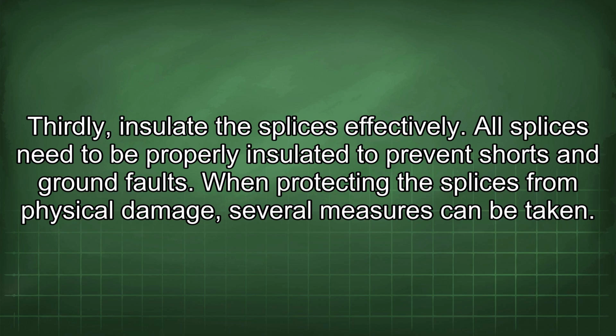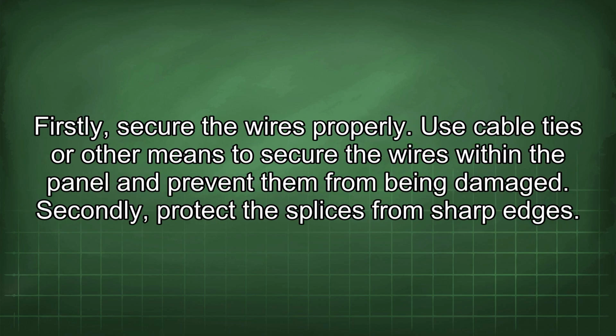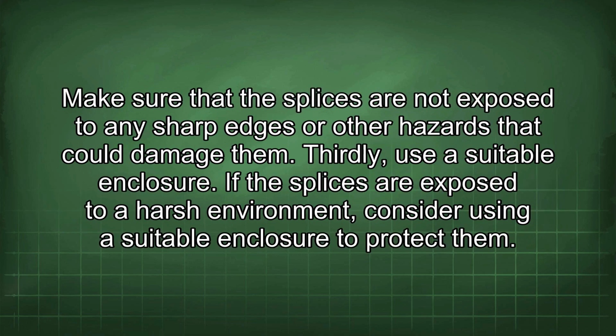When protecting the splices from physical damage, several measures can be taken. Firstly, secure the wires properly. Use cable ties or other means to secure the wires within the panel and prevent them from being damaged. Secondly, protect the splices from sharp edges. Make sure that the splices are not exposed to any sharp edges or other hazards that could damage them. Thirdly, use a suitable enclosure. If the splices are exposed to a harsh environment, consider using a suitable enclosure to protect them.